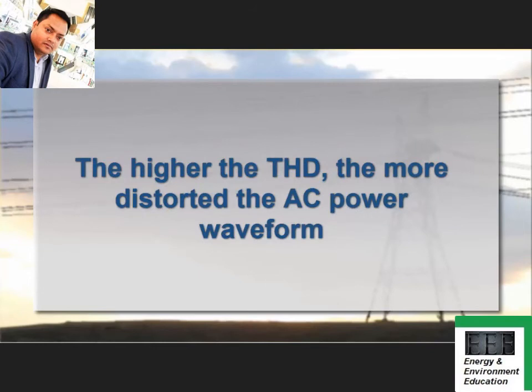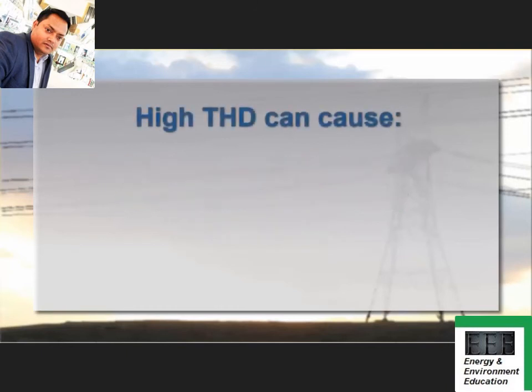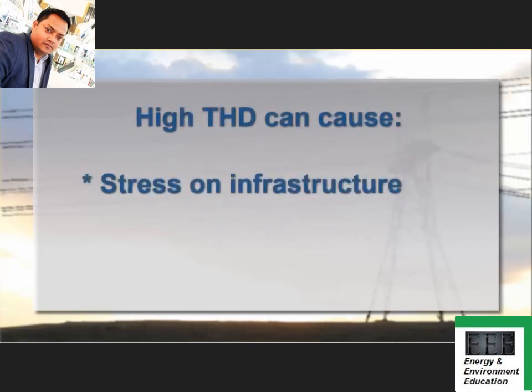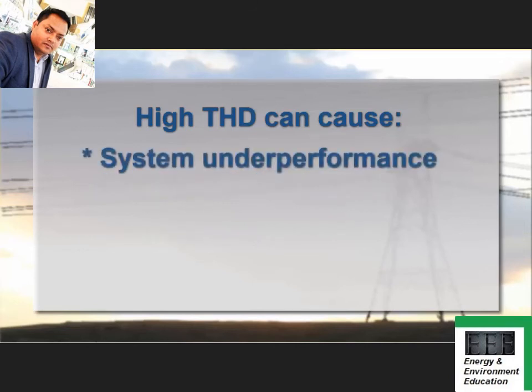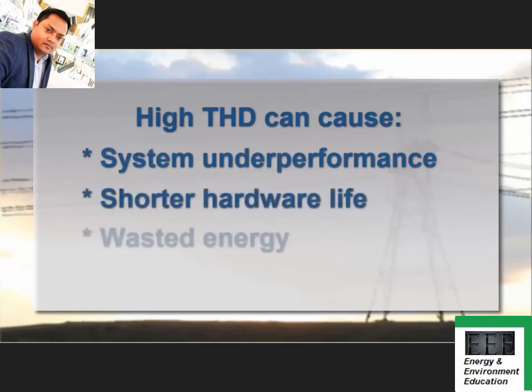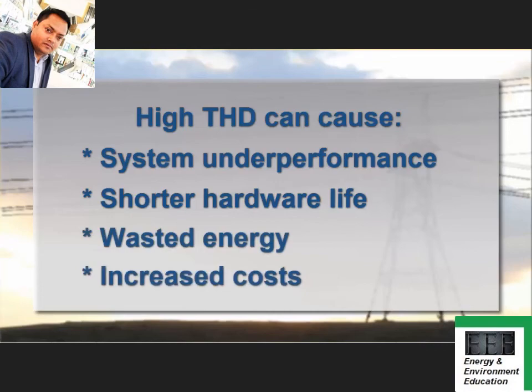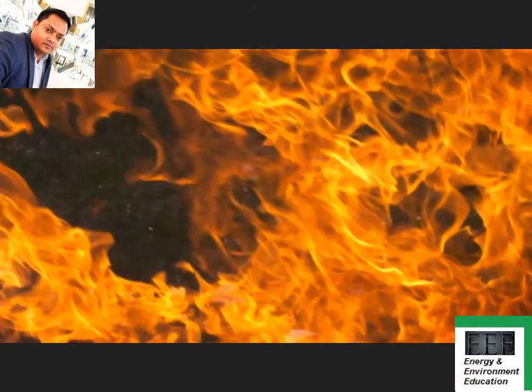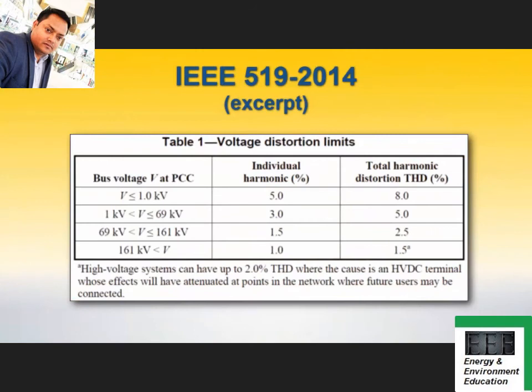The higher the THD, the more distorted the electricity's waveform. A high percentage of THD can stress electrical infrastructure and equipment, resulting in significant electricity dissipated as excess heat. Left unaddressed, harmonic distortion produces issues such as system underperformance, shortened hardware life, wasted electricity, and increased electrical costs. In extreme cases, THD can increase the risk of personal injury. Standards such as IEEE 519-2014 define how much harmonic distortion is allowed for certain types of facilities.